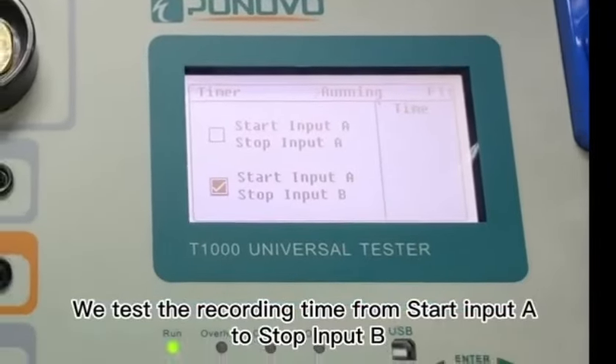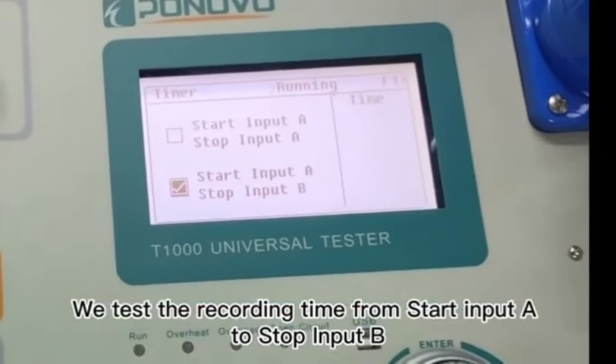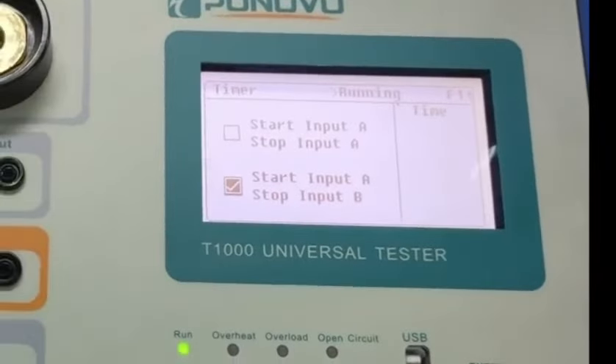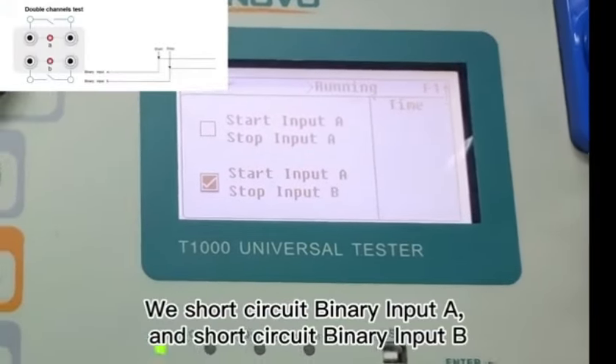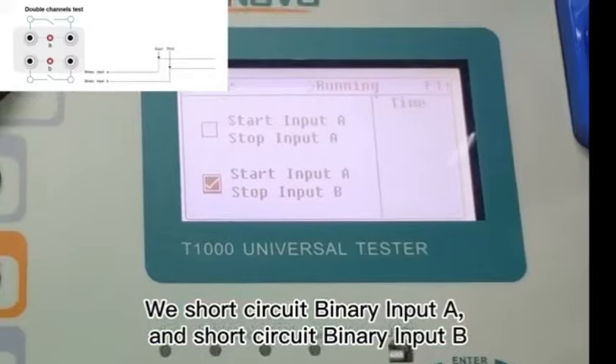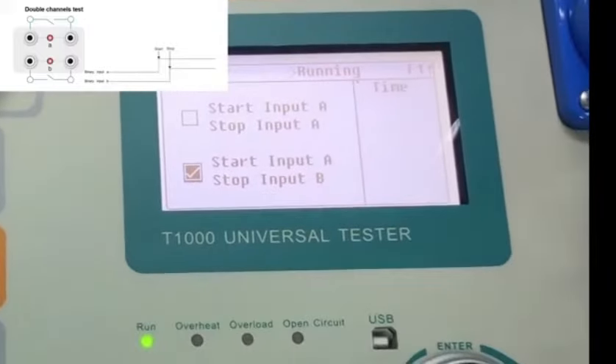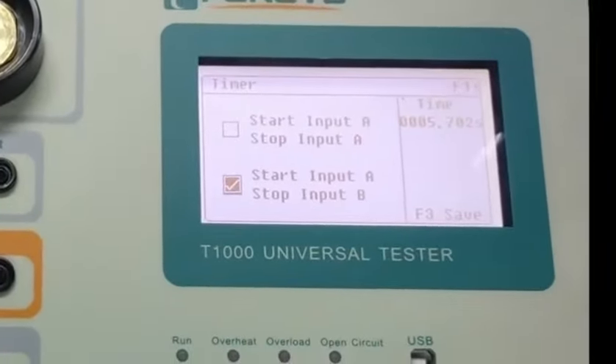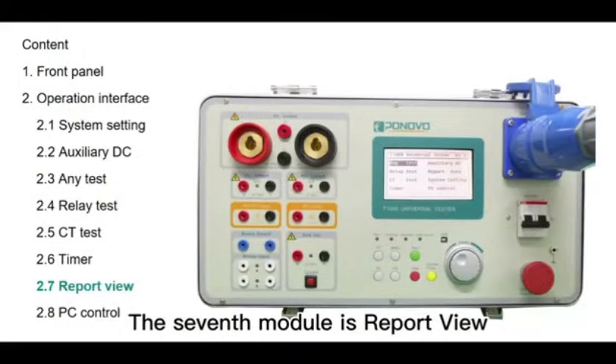We test the recording time from start input A to stop input B. We short circuit binary input A, and short circuit binary input B. Here shows the time. The 7th module is report view.